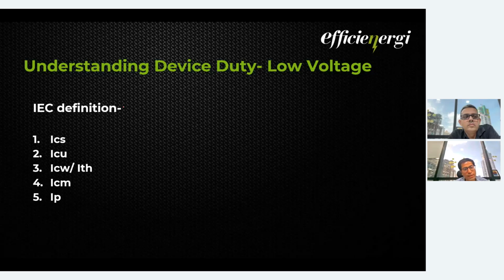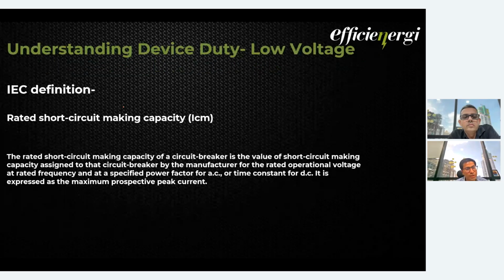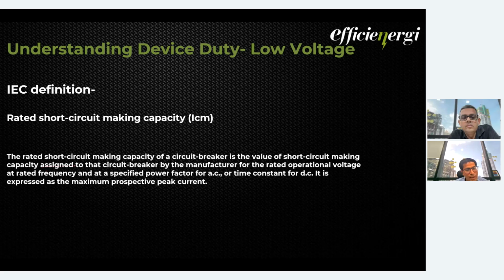So what does IEC say about these definitions? ICM is the rated short circuit making capacity. If you see all these definitions, the words 'assigned to the circuit breaker by the manufacturer' will be there. IEC is not saying that the value should be this or that, but says you assign some capacity to your breaker, at a specified power factor, and after that we will see whether your breaker complies with whatever assigned capacity is given.